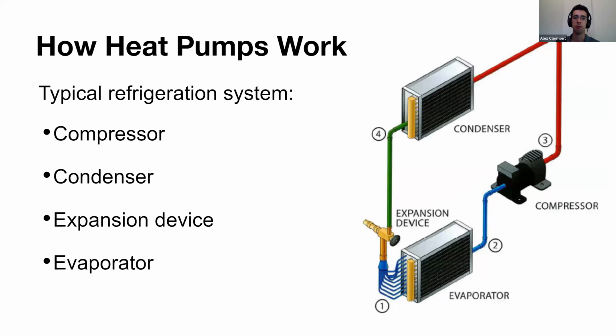Now, you might have seen these before, but these are the basic 4 components of any refrigeration system. These are the compressor, the condenser, the expansion device, whether that's a thermal or an electronic expansion device, and an evaporator as well. In some heat pumps, the expansion device lives at the condenser unit, such as a mini split or a multi-split, whereas in a VRF, which we'll get into in a little bit, the expansion valve lives at the indoor unit.